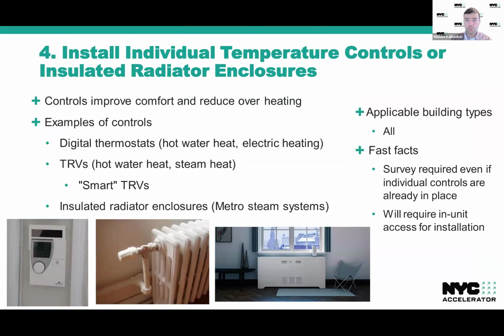Measure number 4 is to install individual temperature controls or insulated radiator enclosures on heating units. So the idea here is that it's very, very easy to overheat spaces. So you want to ensure that you are providing enough heat to keep residents comfortable and to meet housing code requirements, but you don't want to overheat too much because you're using more energy than needed. So controls on an individual level help to improve comfort for residents and reduce that overheating.